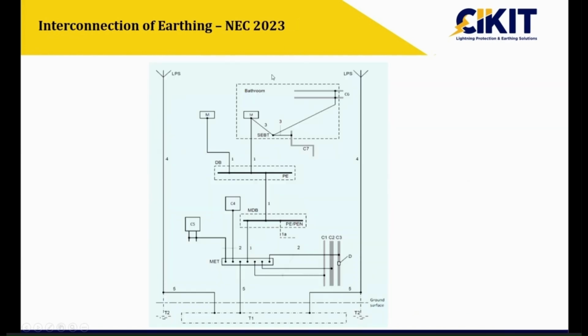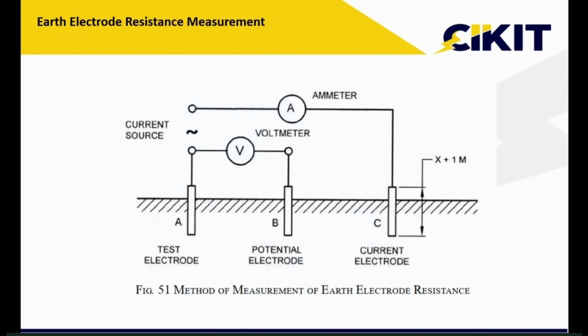This one is the reference from the latest NEC 2023. Here also you can observe that the body earthing of the equipment is connected to the main earthing which is below the ground level. That is, all the earthings are connected below the ground level. So the lightning protection earthing can be interlinked with the earthing of other systems.